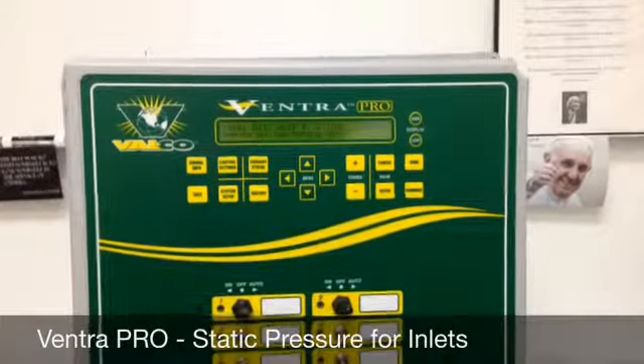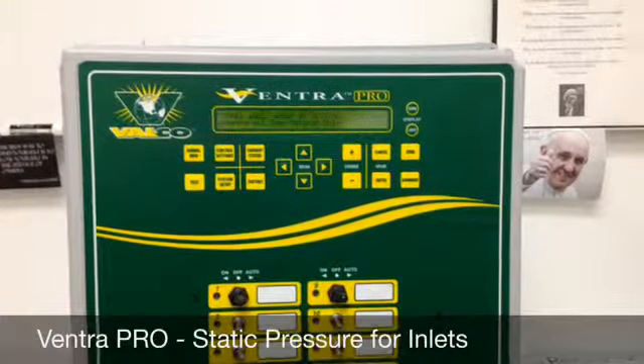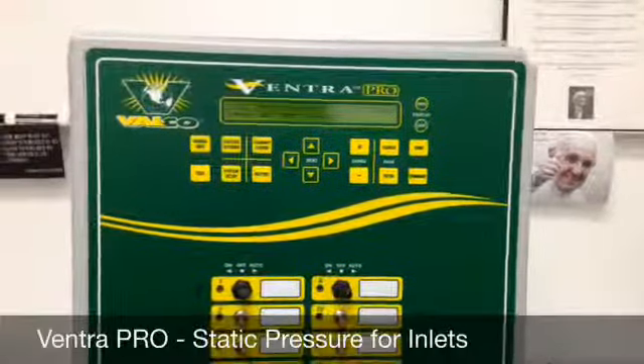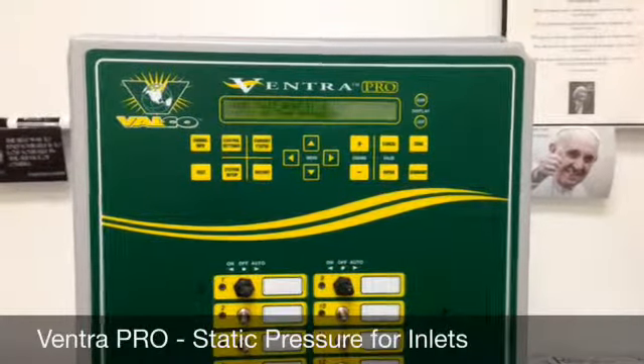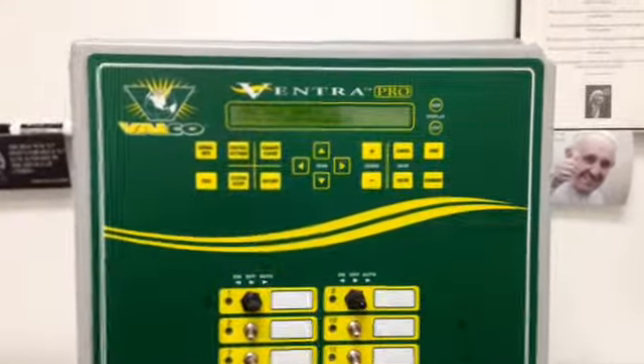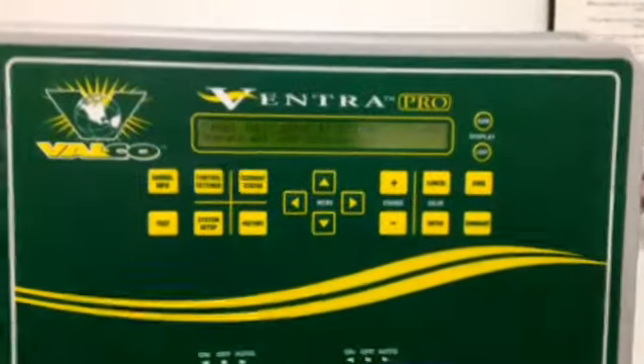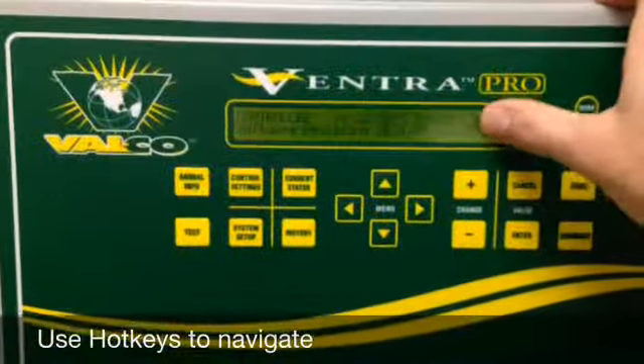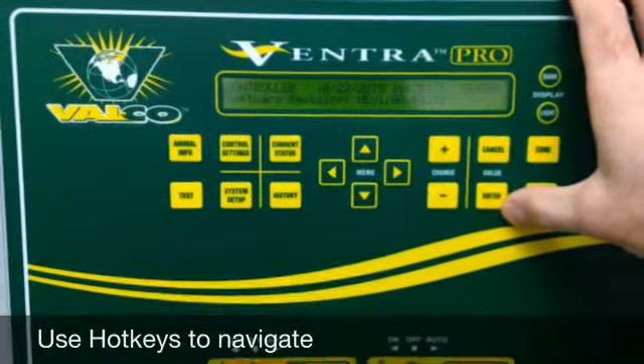Today we're going to be talking about how to program a Ventra PRO controller to have the tunnel inlet or tunnel curtain operate off of static pressure using a static pressure sensor.